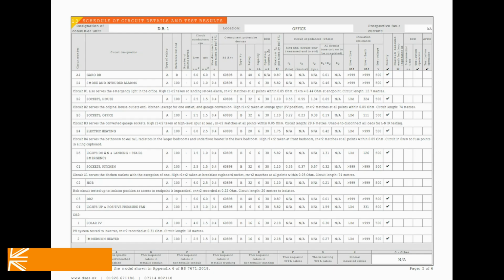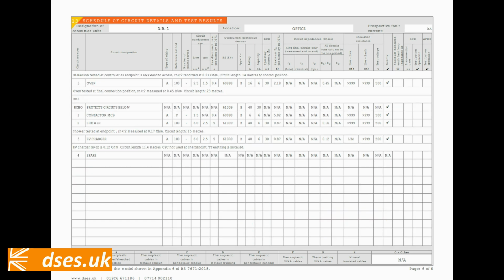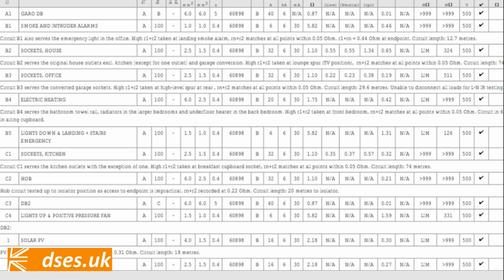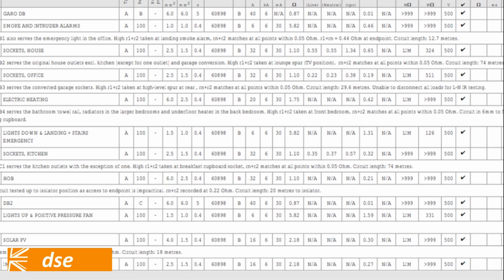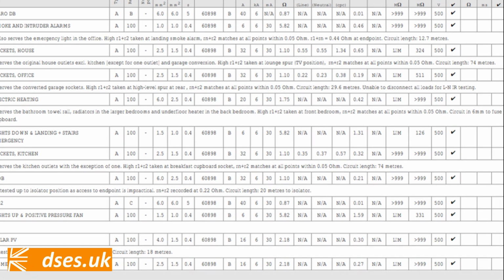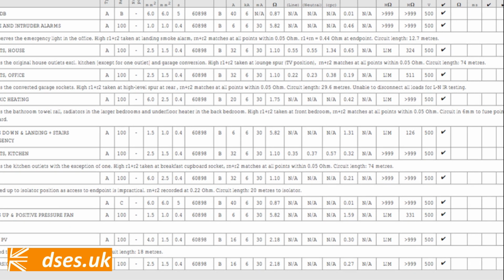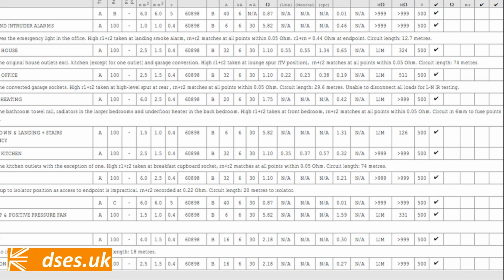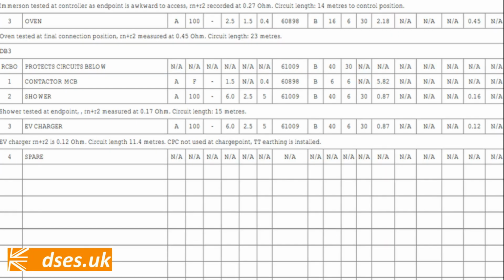I've compiled them all onto one schedule, despite there being split over 3 boards, but that's just for ease of display here. Now that the upgrade is finished, I will author a new electrical installation certificate to cover all this, of course. A few things of note: no RCD testing took place last week because the RCDs were to be decommissioned, of course. As already mentioned, line to neutral IR testing has been omitted where it's just too impractical to wire out all the fixed loads, and I've omitted ZS testing where I can't safely connect my MFT via a plug and socket arrangement. Crucially, as I showed earlier, I've measured Rn plus R2 per circuit to compare it with the line figure, and I've calculated circuit length based on those readings.